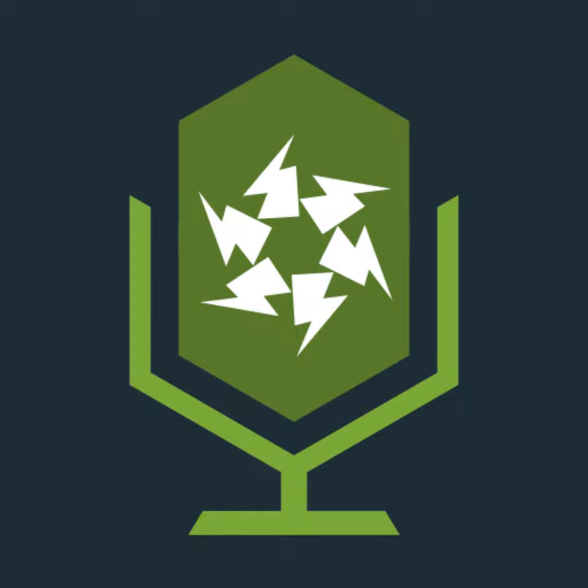Both of them can go fault to earth, L1 to earth and L2 to earth, as you see here. They can both fault to earth at 55 volts. So if I had a fault between L2 and earth, a short, a damaged piece of equipment, the current will flow from there and then flow back, and you'll see it goes into half the winding. As it's only going through half the winding, it's only half the voltage within this earth fault loop. So we have half the voltage in the fault scenario.